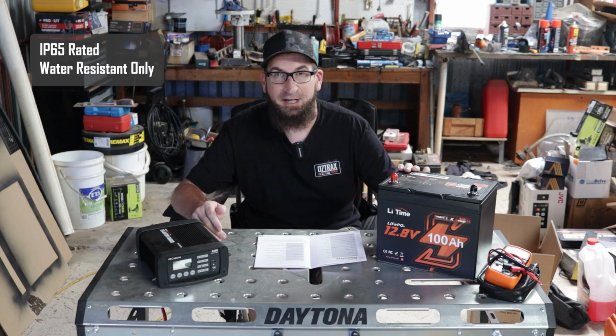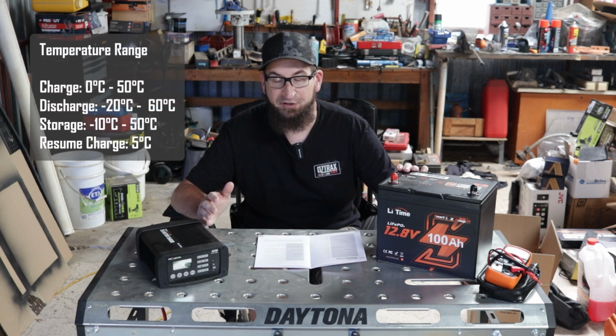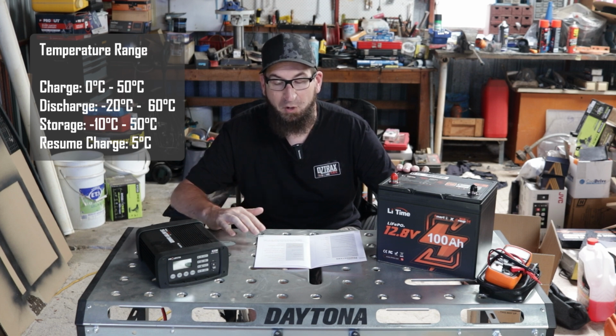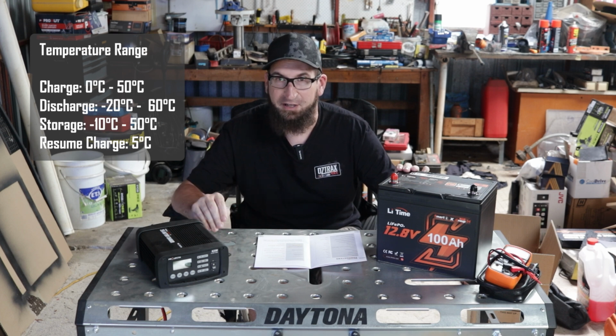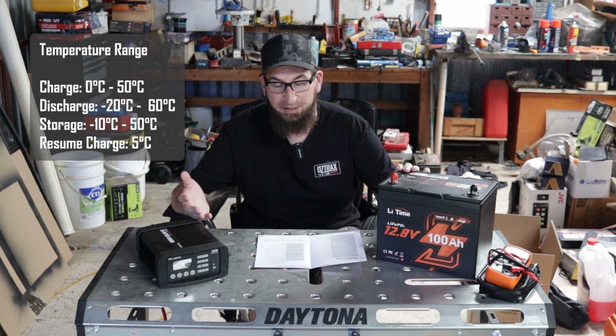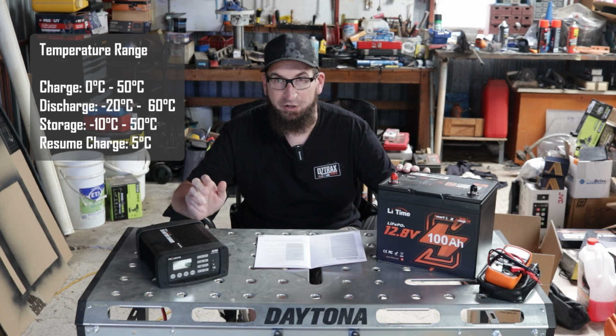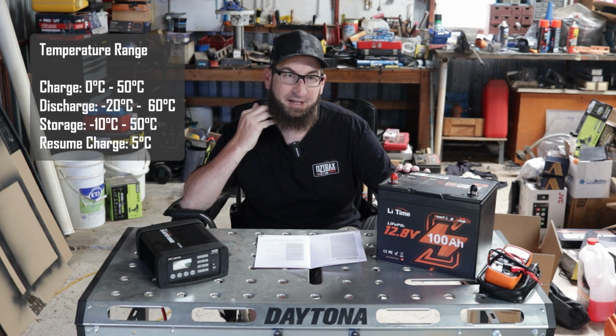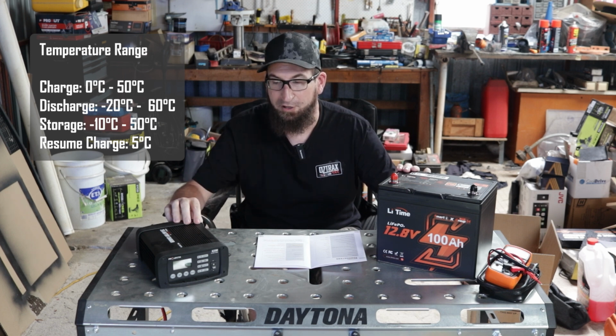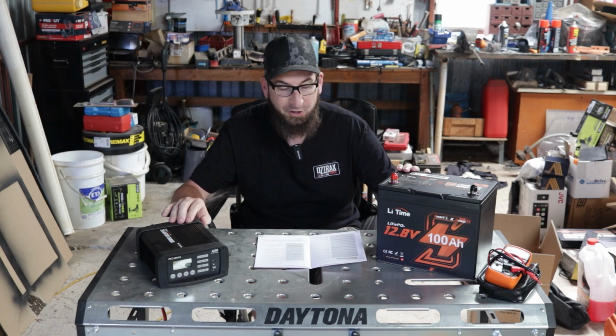It is IP65 rated, so if you're looking at doing water crossings, not a good idea to put this one under the bonnet. Temperature range for charging is 0 to 50 degrees Celsius. I had it at 52 degrees, not an issue. Discharge is minus 20 to 60 degrees Celsius, also not an issue. Storage is minus 10 to 50 degrees - doesn't get to 50 in Australia, and even at 52 degrees it cooled down so it wasn't a problem. There's also a low temperature charging protection function that resumes charging at 5 degrees Celsius, so if you're in a cold climate, like the Alpine region in Australia in winter, you should be fine.